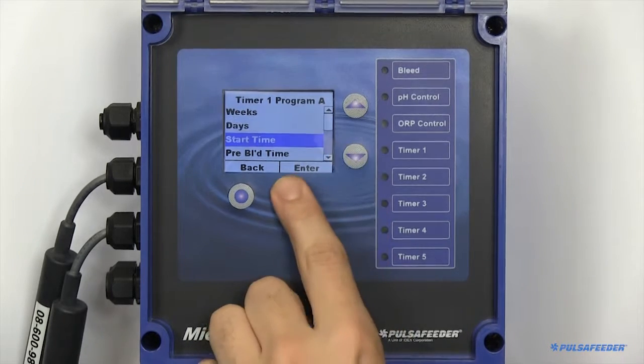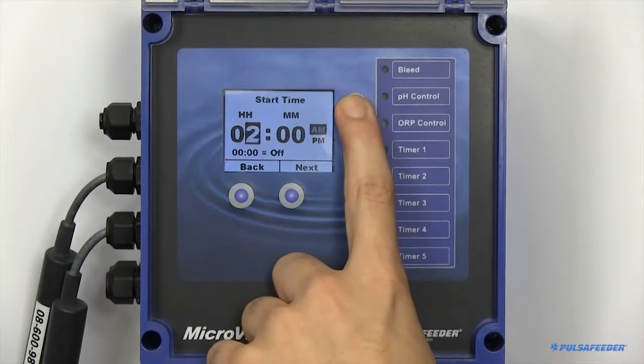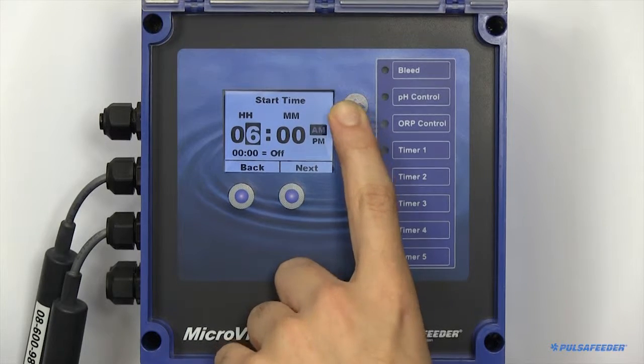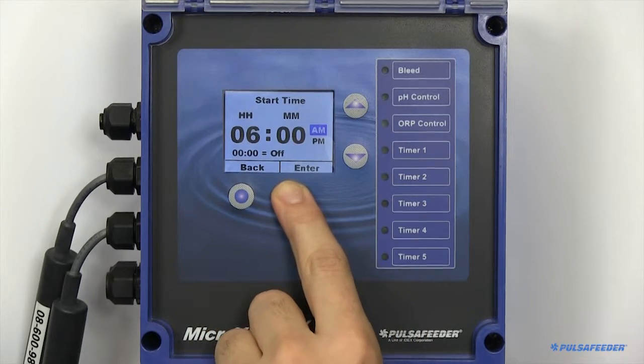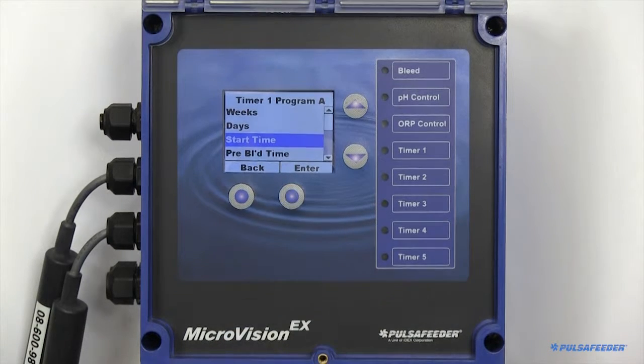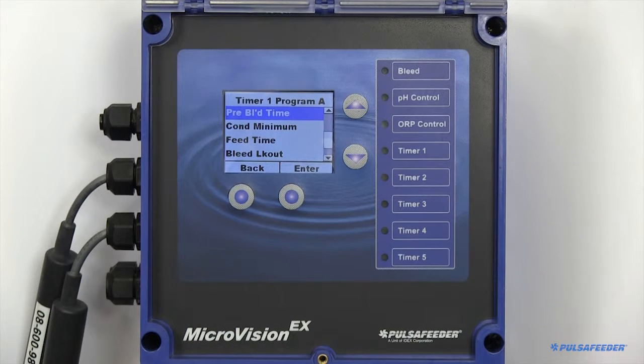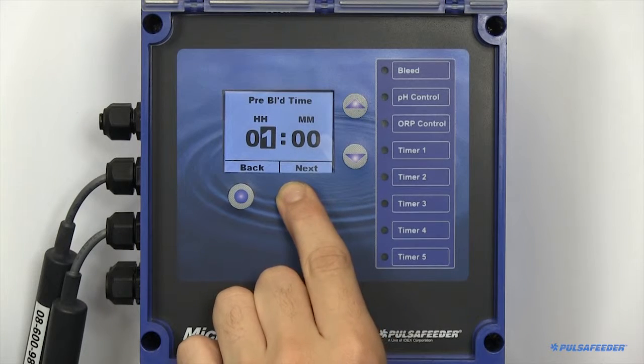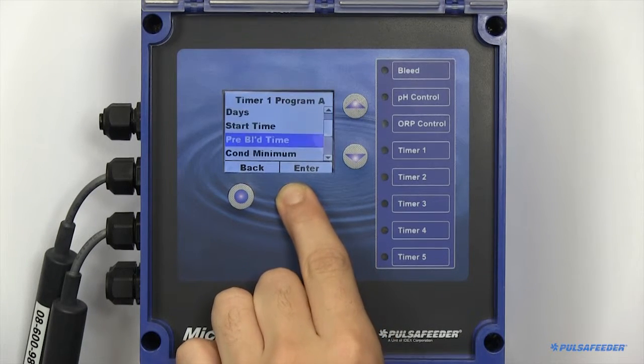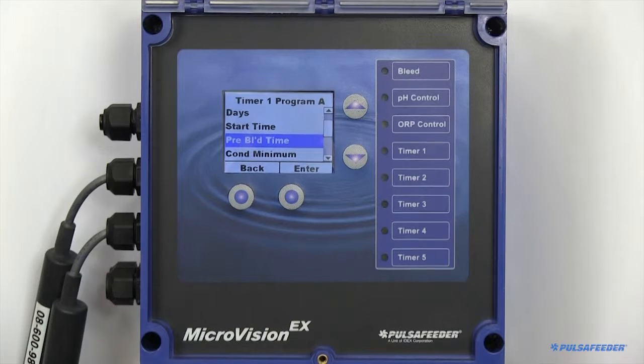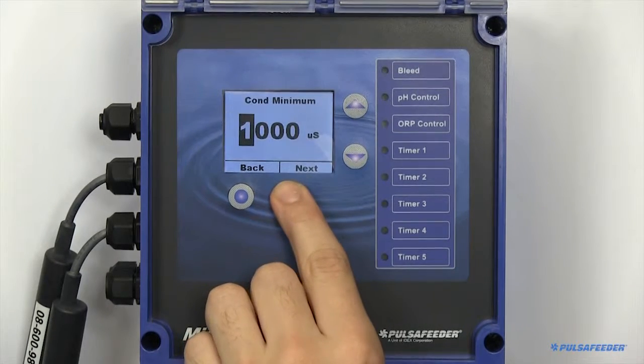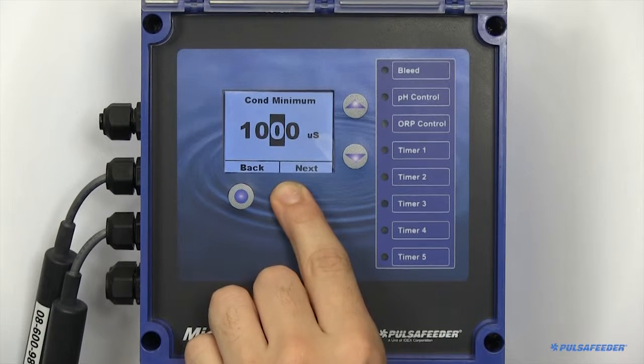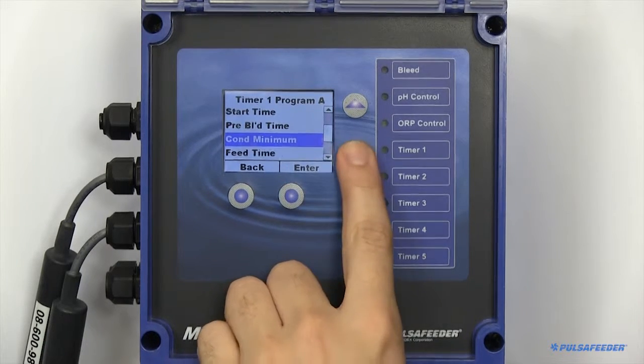The start time is when you would like to either begin your feed cycle, or a prebleed, if applicable. A prebleed time is the maximum amount of time you would like the bleed function to be force enabled prior to a feed cycle. If there is a minimum conductivity you would like the tower to reach to immediately begin your feed cycle, this can also be set.